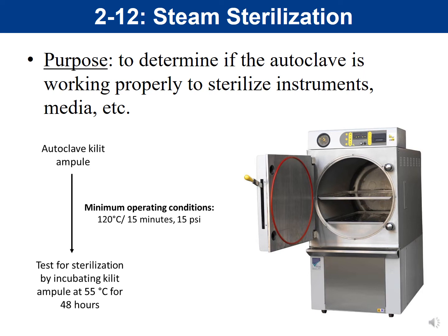The next activity is steam sterilization, which connects to the temperature experiment. The purpose is to determine if the autoclave is working properly to sterilize instruments, media, etc. The autoclave is essentially a large pressure cooker using pressurized steam to exceed 100°C. Minimum operating conditions for sterilization: 120°C for 15 minutes at 15 pounds per square inch (PSI).